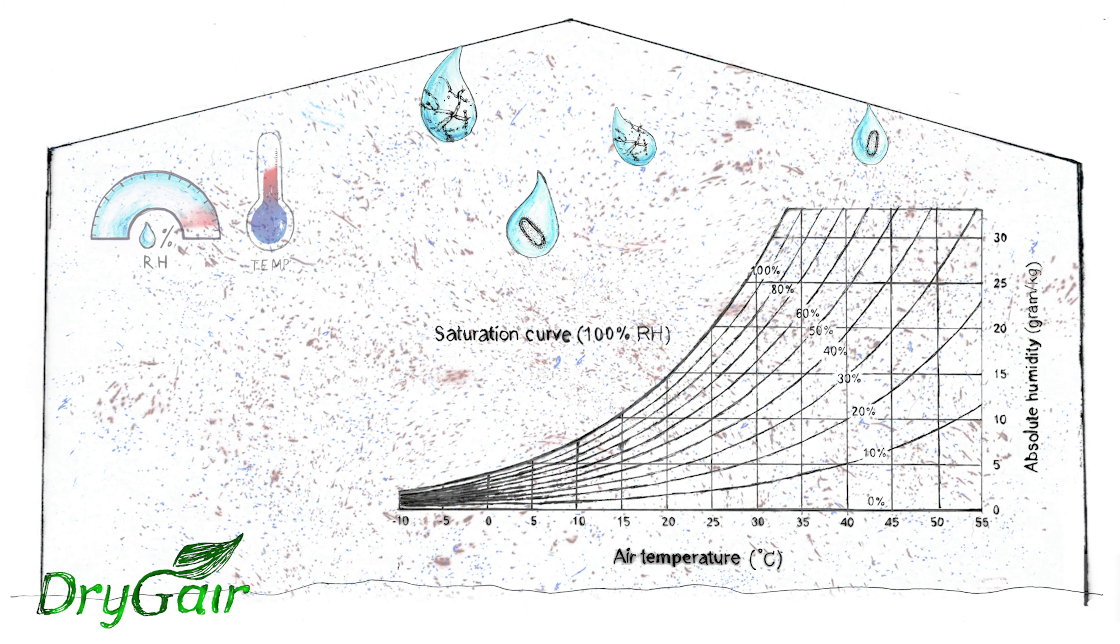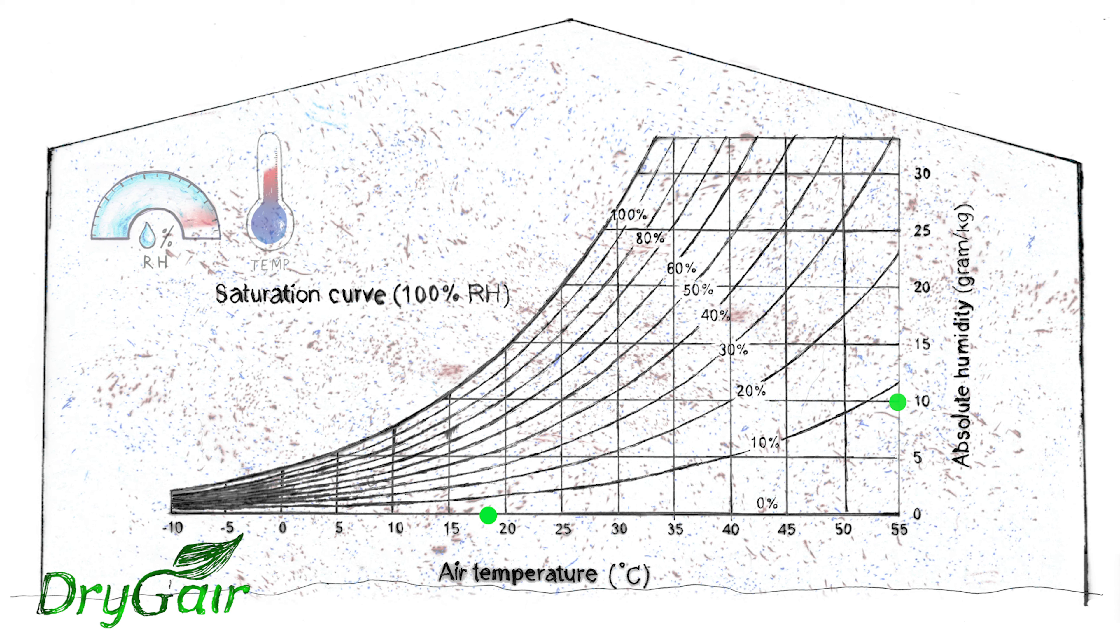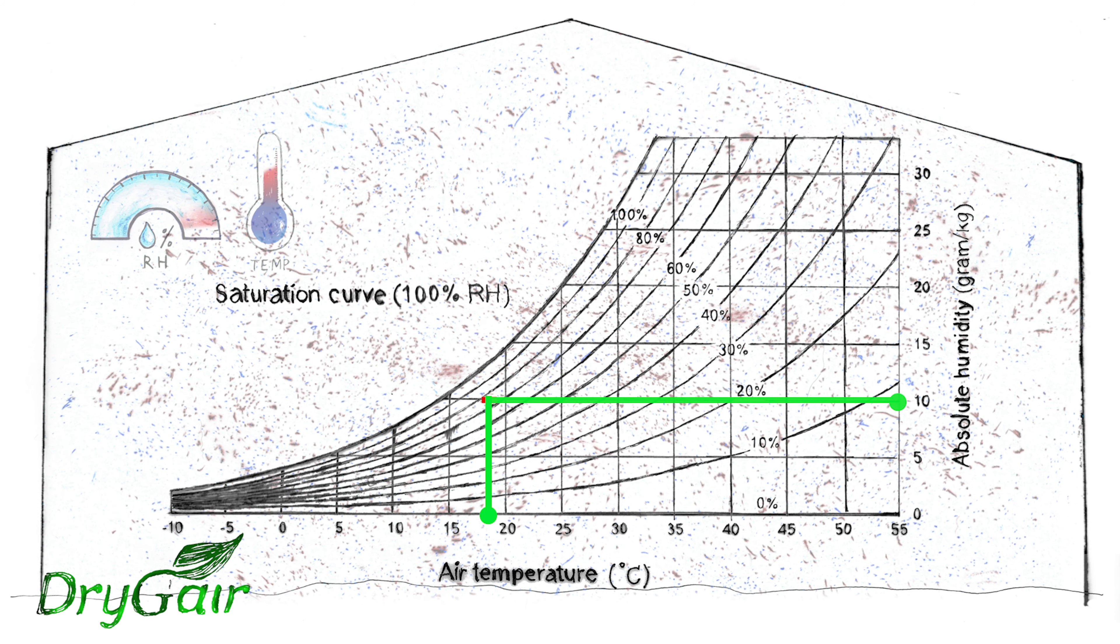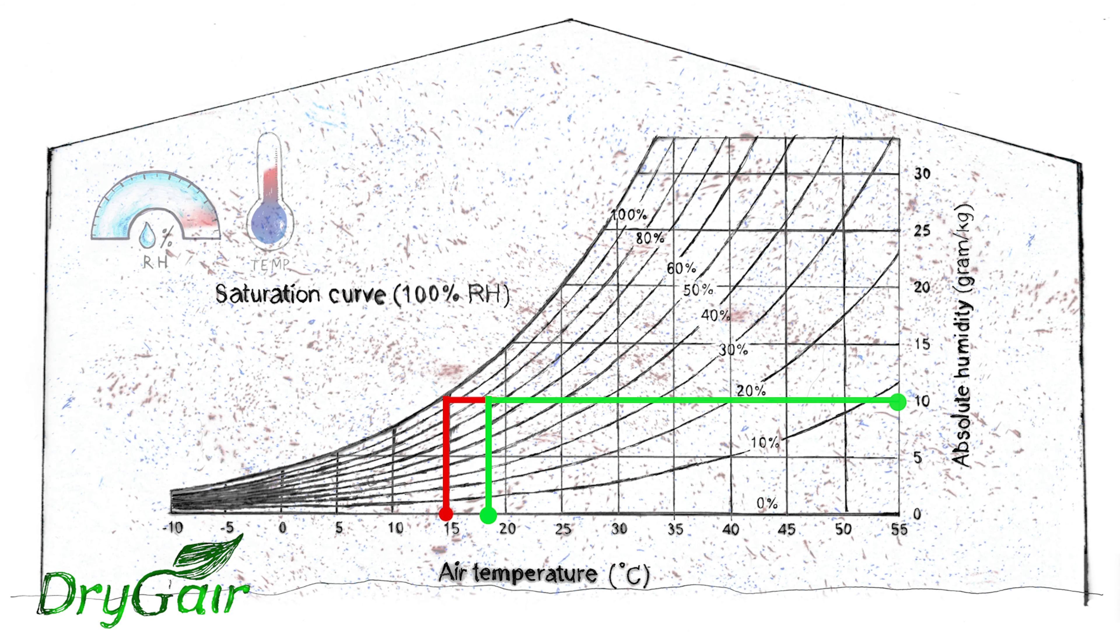Understanding the psychrometric chart helps to avoid the dew point. From any given point of temperature and absolute humidity content, draw a line to the saturation curve. The corresponding temperature underneath will be the dew point.